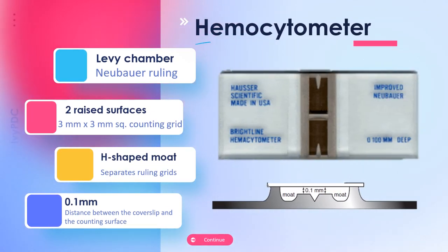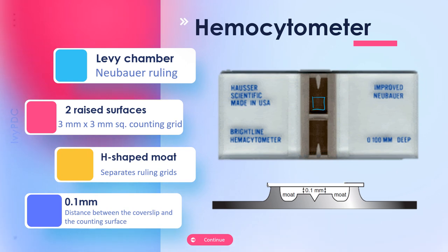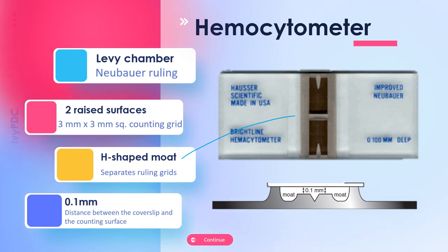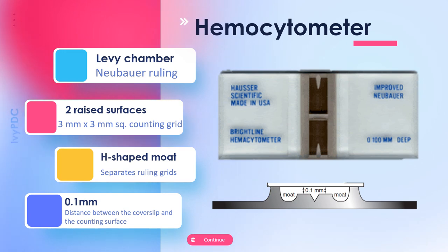The manual cell count uses a hemocytometer or a counting chamber. The most common one is the Levy chamber that uses an improved Neubauer ruling. It is composed of two raised surfaces, each with a 3 mm by 3 mm square counting area — chamber one and chamber two. These two raised surfaces are separated by an H-shaped moat. At a side view, the distance between the cover slip and the hemocytometer is 0.1 mm, which will be important in the computations.